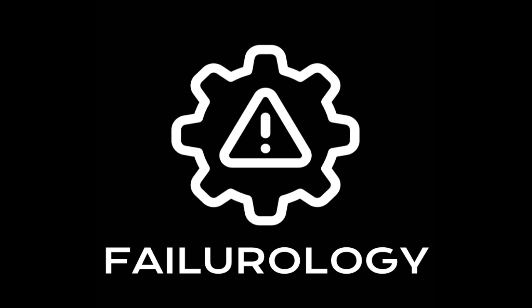In a fire situation, you really want your automated systems to work, because if it's in manual mode, somebody's got to identify that there's a fire or respond to an alarm bell and flip some switches, and the pumps would have to get back up to pressure. There's probably a better way of solving this, but unfortunately the pumps were in manual control when this Piper Alpha incident happened.